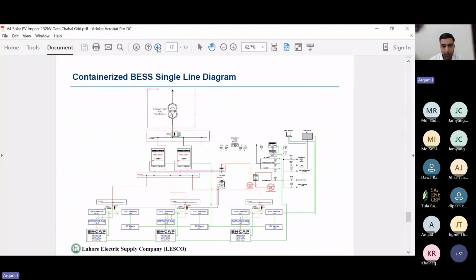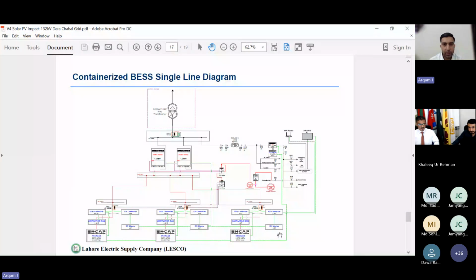In terms of the high level design of the battery energy storage system, at the bottom we have the storage cells. These are containerized solutions to be installed right at the substation switchyard, and they will have storage cells in them. Then upstream we have the 11 kV or medium voltage network, where it will be interfaced into the medium voltage switchgear room of the substation with a step down transformer from 0.69 kV to 11 kV. So it can step up and step down at the same level.